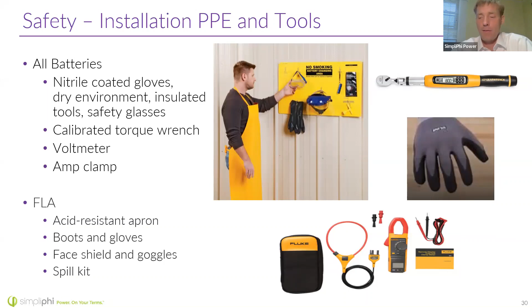All they would have needed to use, instead of tightening the terminals with a metal wrench, is a wrench with a rubber handle. I specify getting a torque wrench because we specify torque settings on the bolts as you tighten down the terminals. We get batteries back because people use an impact driver, which can break the brass bolts on the terminal. I recommend an insulated torque wrench like this. I have a personal story where a battery got so hot the lead melted and dripped down inside, melting through the plastic cover as well. So be careful, and having the right insulated wrench can save you from that problem.